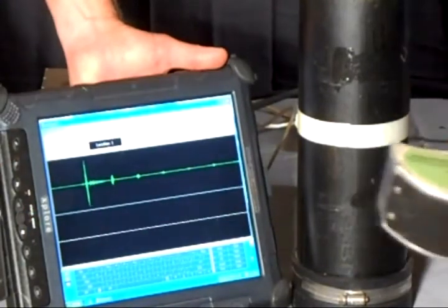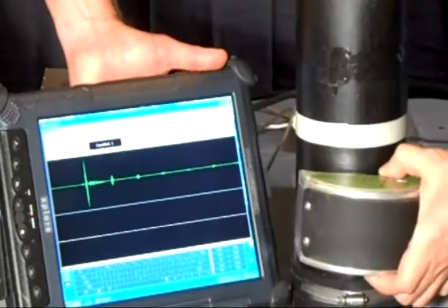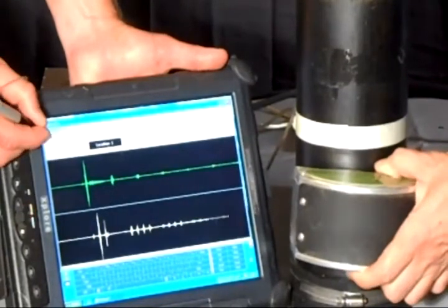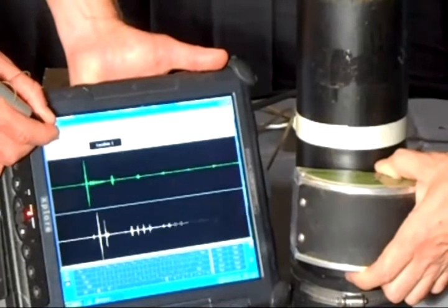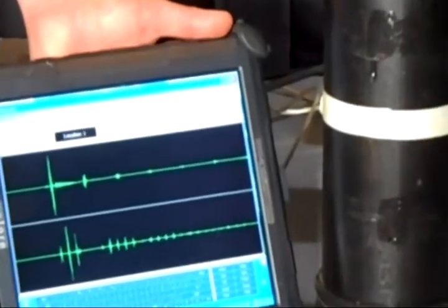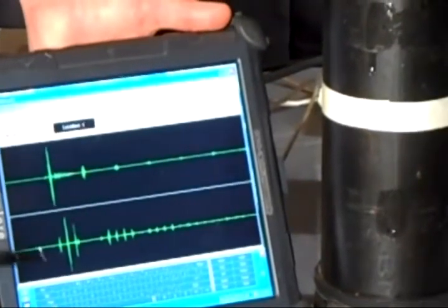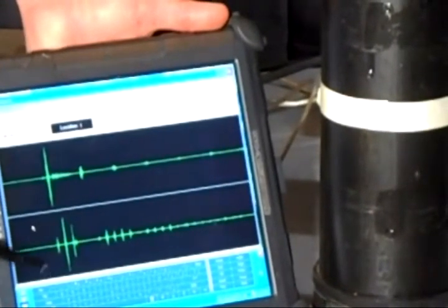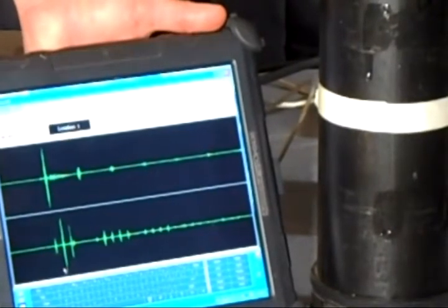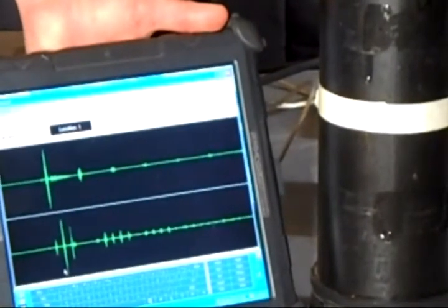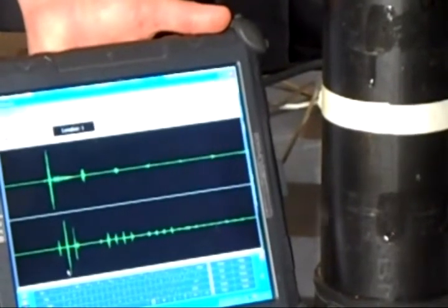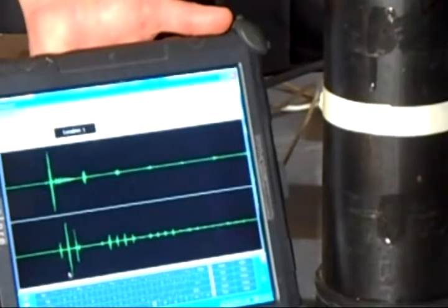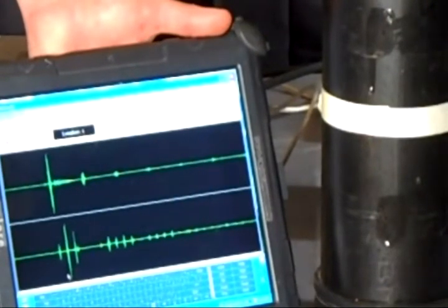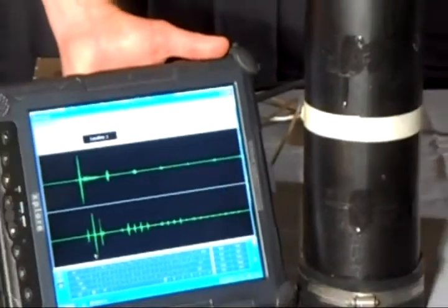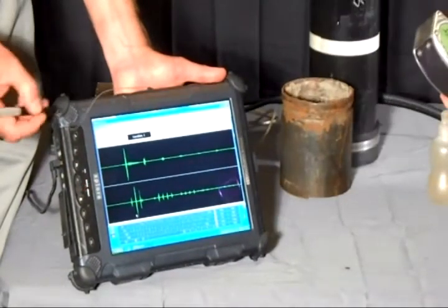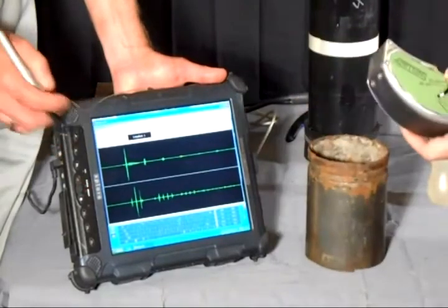So now I'm going to move down to where there's water. Let's pretend that there's water that's trapped inside your dry pipe system. Here you can see that there is a significantly different type of waveform here. And what's happening is some of the sound energy that normally travels through the wall of the pipe is leaking into the water inside the pipe, which is indicated by those second set of waveforms there that are not present on the upper signal. That energy tells us that there is water inside that pipe, which is a good thing in a wet pipe system, but in your dry pipe system, you don't want to see that. Conversely, we can also find air pockets that are trapped in wet systems using the same thing, just flip-flopped.